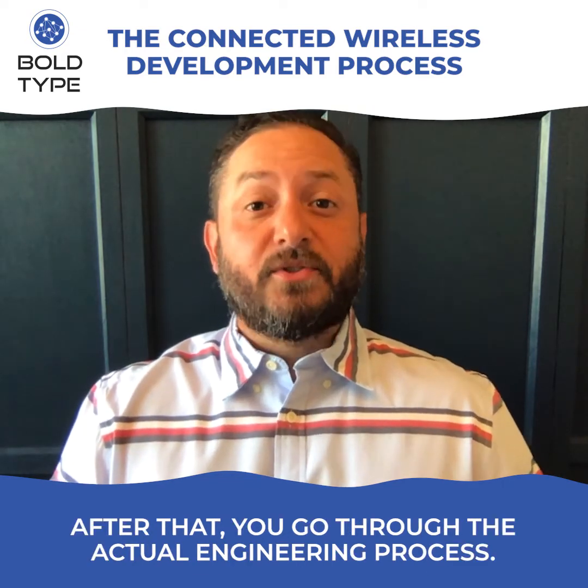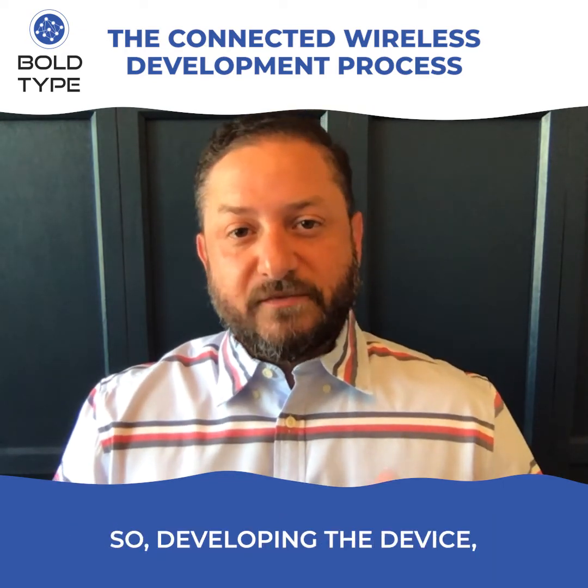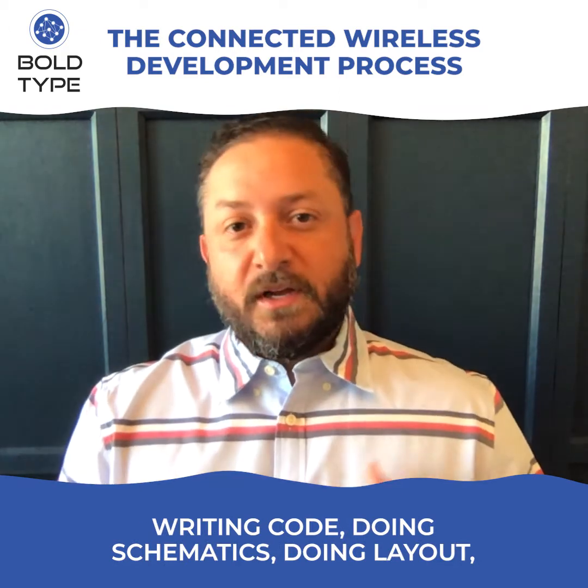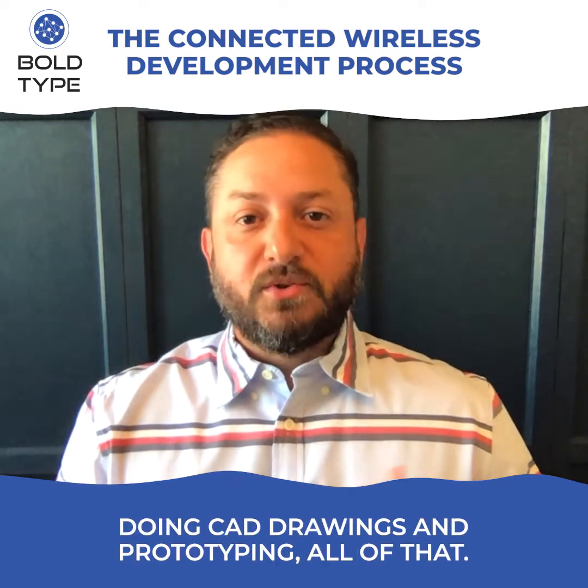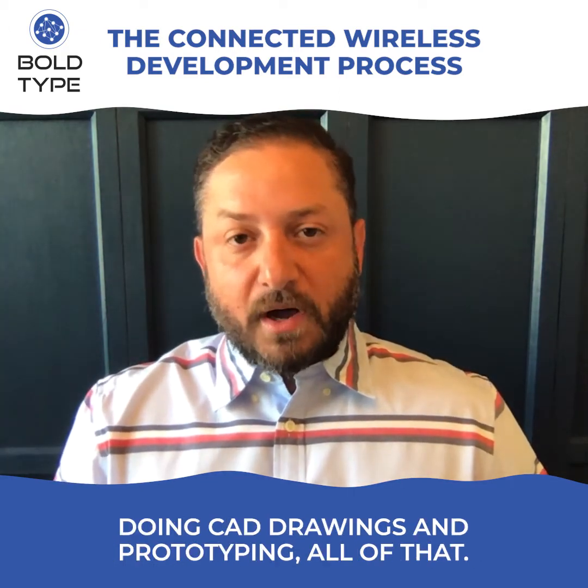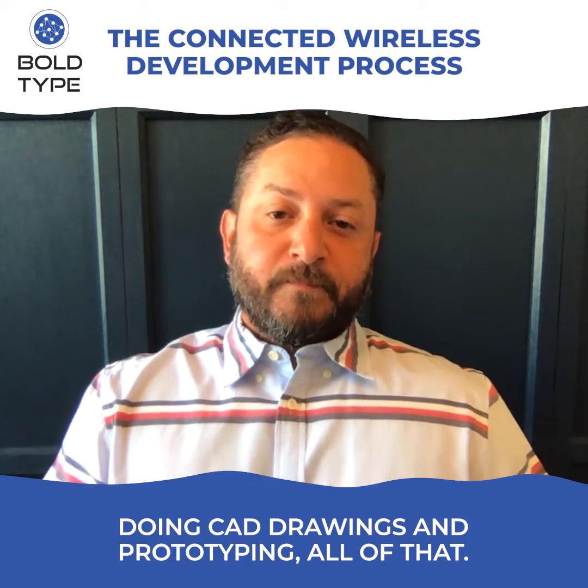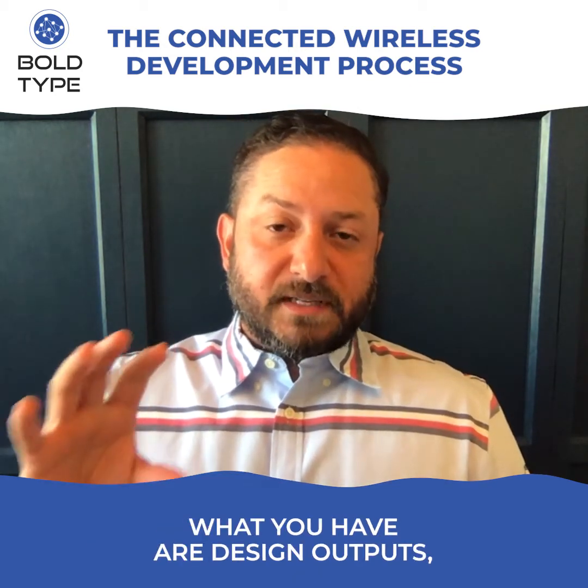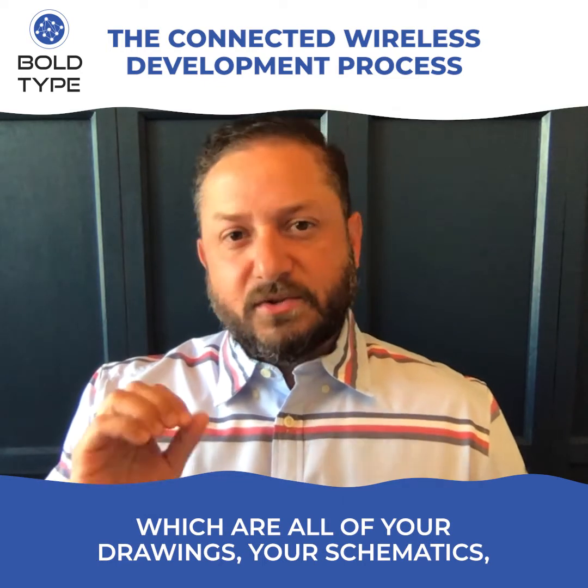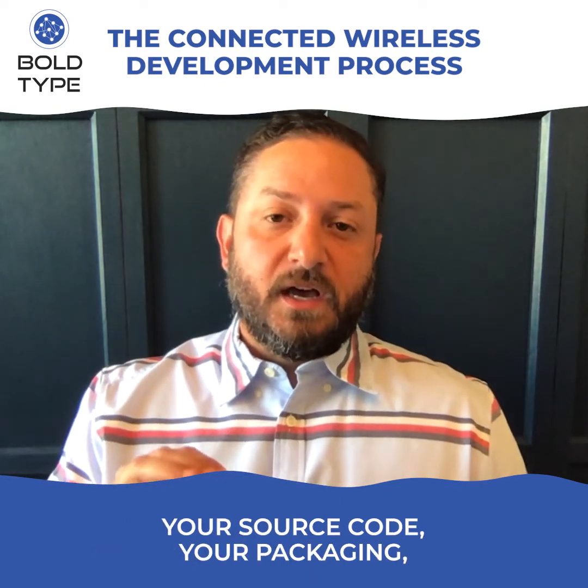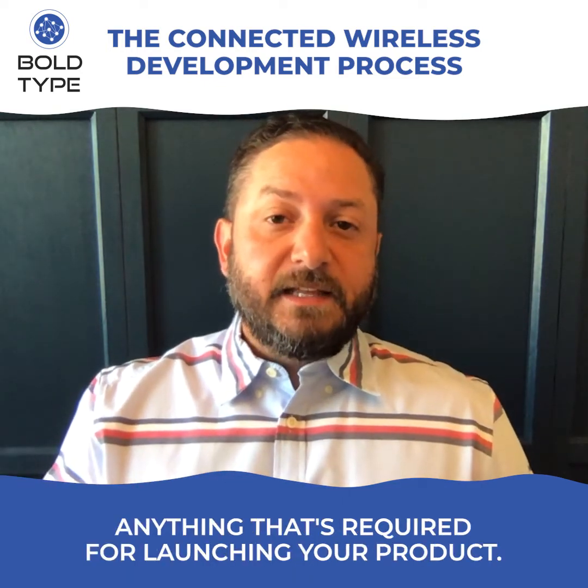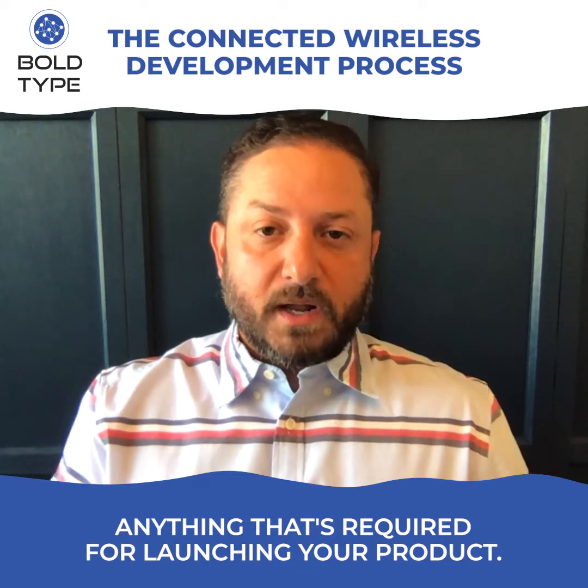After that, you go through the actual engineering process. So developing the device, writing code, doing schematics, doing layout, doing CAD drawings and prototyping, all of that. And at the end of that phase, what you have are design outputs, which are all of your drawings, your schematics, your source code, your packaging, anything that's required for launching your product.